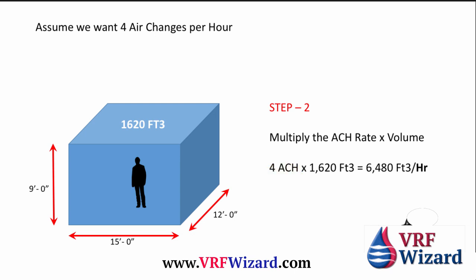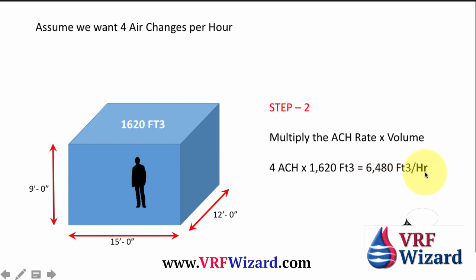Take your four air changes and multiply by the cubic feet of the room to get the total cubic feet of air that we need to remove in the hour. Four air changes per hour is equivalent to 6480 cubic feet for this room volume — that's four times the volume.